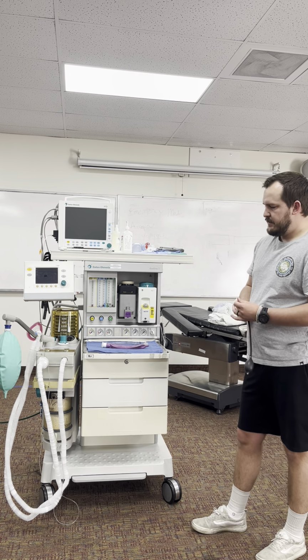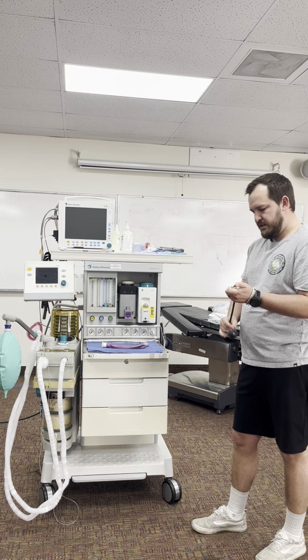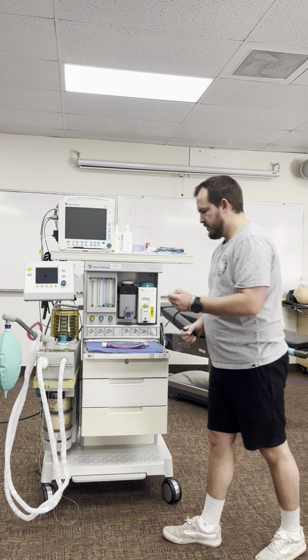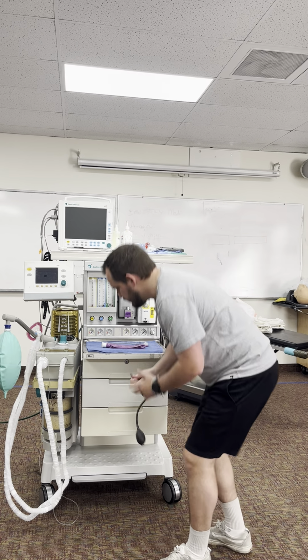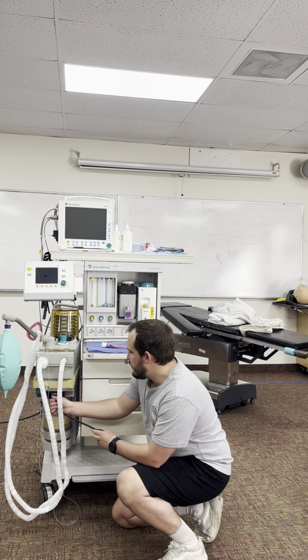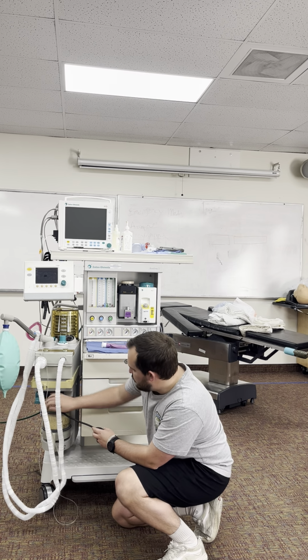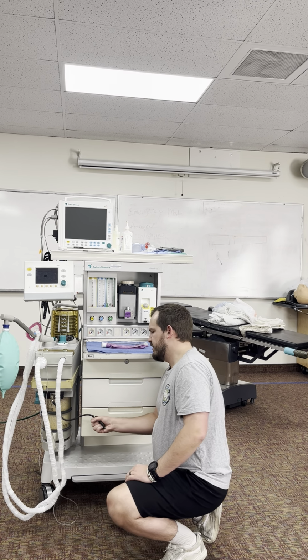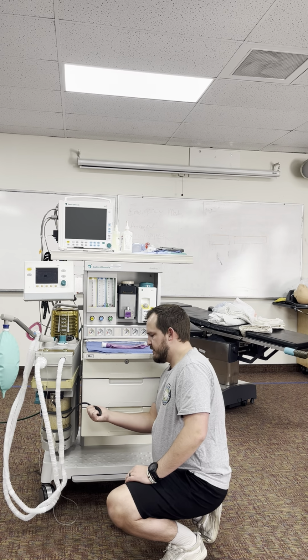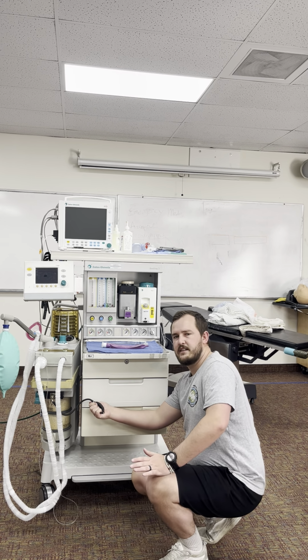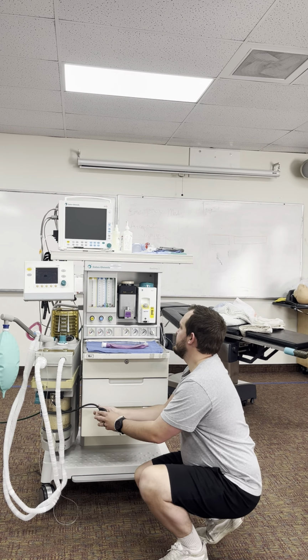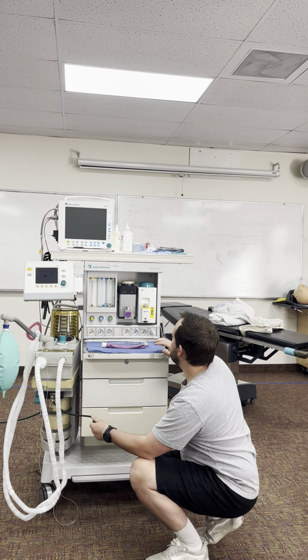And to do that, I am going to double check this first, which is my suction bulb. It's good. So I'm going to hook it into the common gas outlet. I'm going to open up my common gas valve, and I'm going to do this until it occludes and holds. It's got to hold for 10 seconds. It does. That checks my low pressure system.